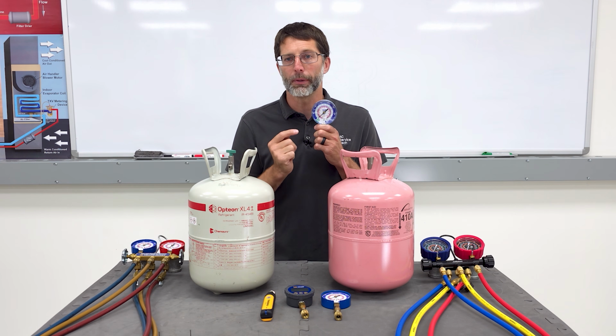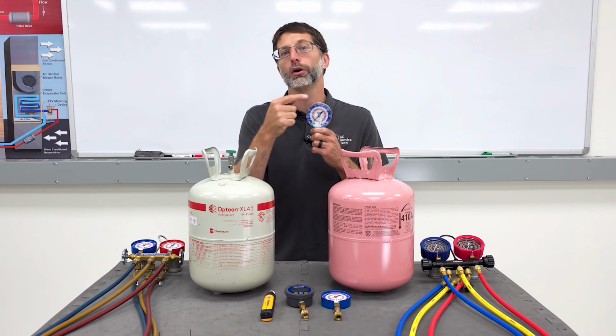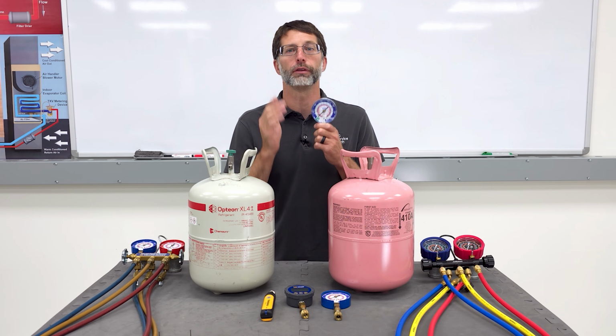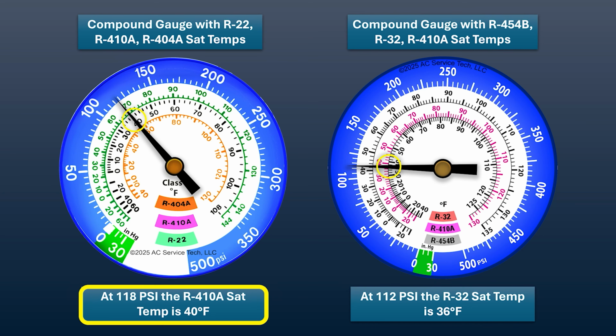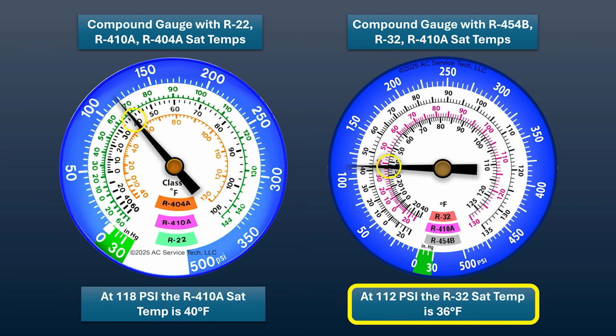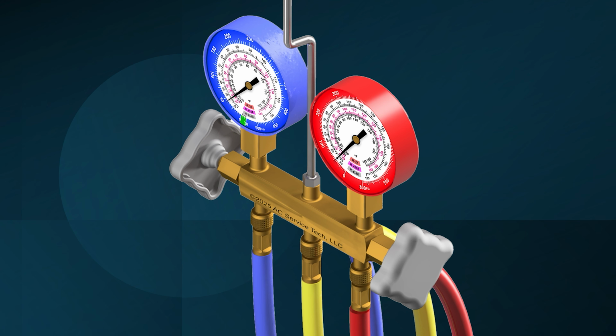The needle on a compound gauge points to the outer pressure ring while also lining up with the saturated temperature of the 3 refrigerants in the inner rings. Figure 4-25 shows a gauge pressure of roughly 118 psi, which aligns to the R410A saturated temperature of 40 degrees Fahrenheit. Figure 4-26 shows a gauge pressure of roughly 112 psi, which aligns to the R32 saturated temperature of 36 degrees Fahrenheit. A compound manifold gauge set for air conditioning typically includes 1 blue low side gauge, 1 red high side gauge, and hoses. See figure 4-27 and 4-28.